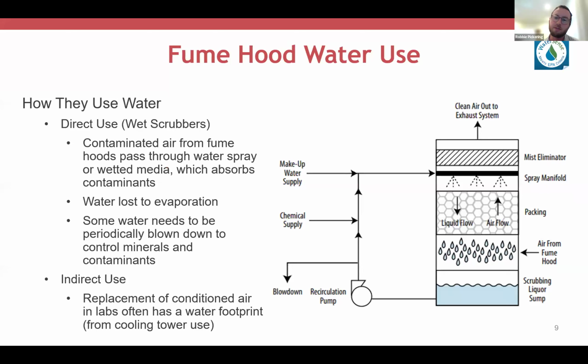Fume hoods with wet scrubbers are the direct use. Wet scrubbers use water to remove contaminants from the fume hood exhaust prior to it being released to the atmosphere. Air that's ventilated through these fume hoods is passed through a water spray or wetted surface. During this process, some of the water is evaporated, and some water also needs to be periodically blown down to help control mineral buildup and contaminant concentration. So this is how fume hoods can directly use water.